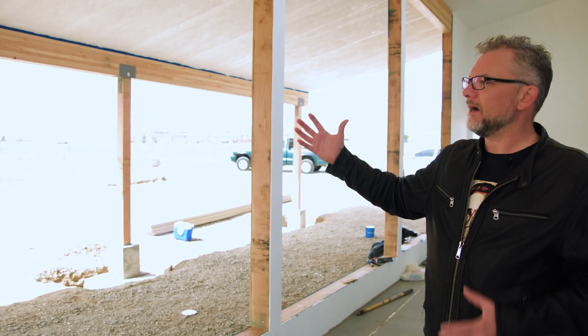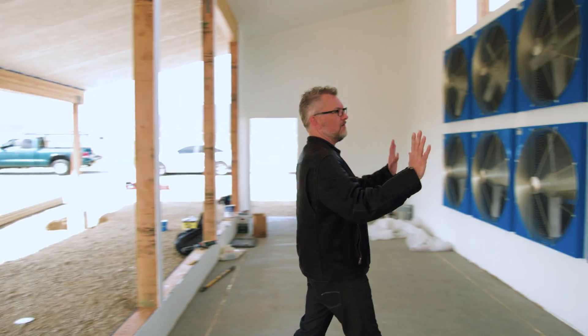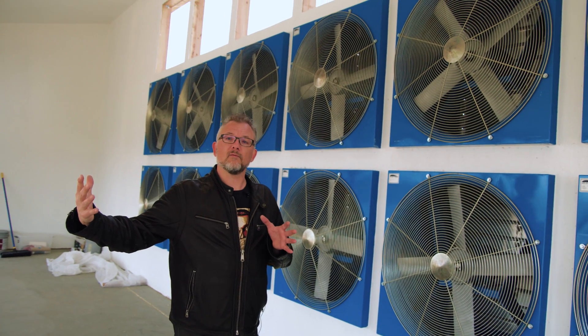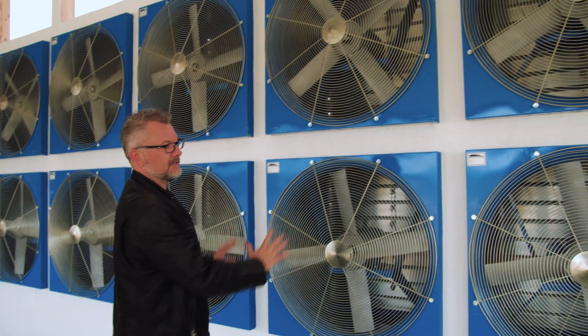What we're standing inside is basically a giant mining box — it's like being inside of an actual Bitmain S9. You've got a tremendous amount of fans arrayed along one wall, and on the other side you've got an array of intakes. The air flows in from this side, moves through the back of the pod, and flows out through the fans. We'll have our miners in racking here so the air really has no other way to go other than through the miners as cool air and out through the fans as hot air. It's a very short throw — I can almost touch the walls from side to side.